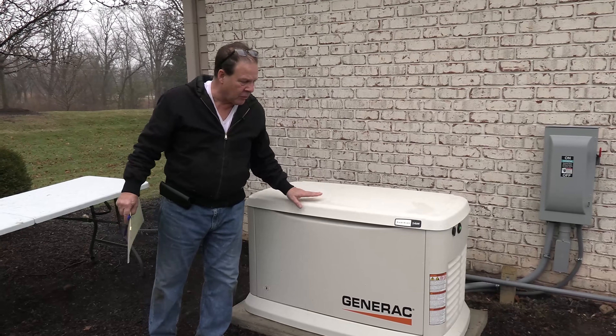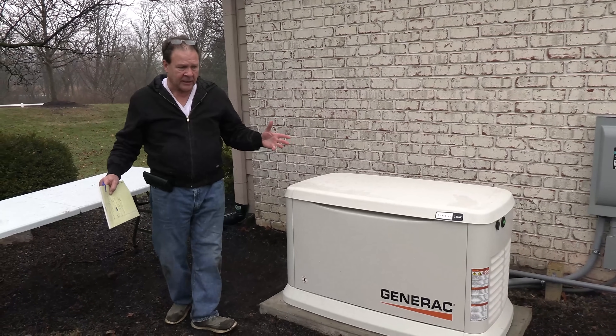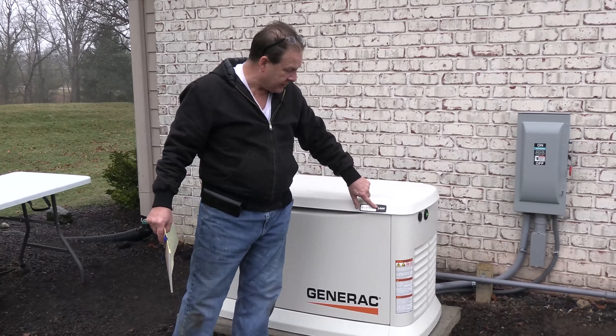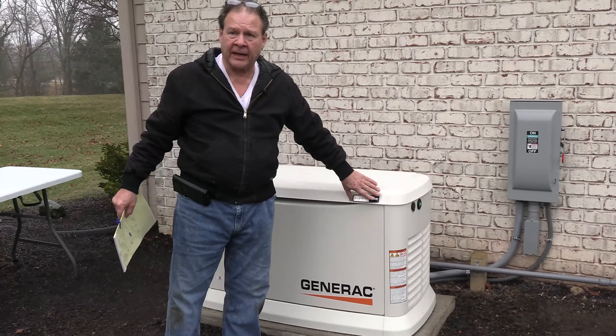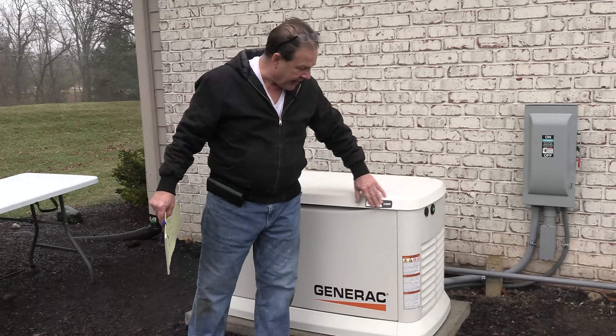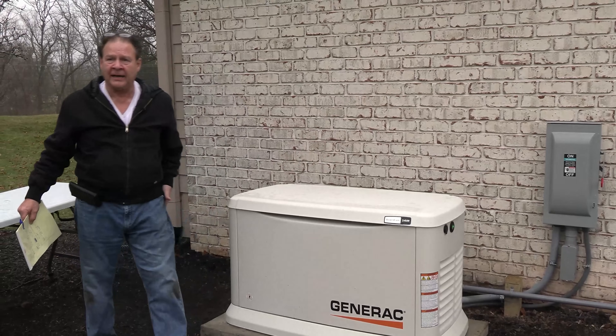So if you decided that you want a whole house generator, this one's 24-kilowatts. The next question is, what's the fuel source going to be? If you're out on a farm and you're using liquid propane, that's one thing. In our case, we've got natural gas. When it says 24-kilowatts, that's on liquid propane — it's derated to 21-kilowatts on natural gas. So these things run more efficiently on liquid propane. That's another reason, if you run natural gas, to buy the biggest one you can. You don't want to buy a 22 or an 18 that's going to get derated down beyond that.